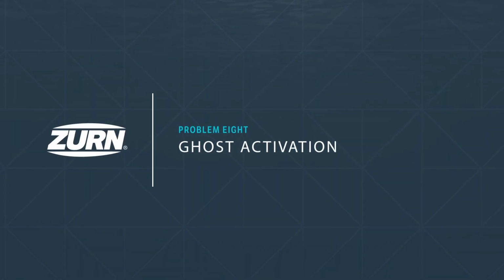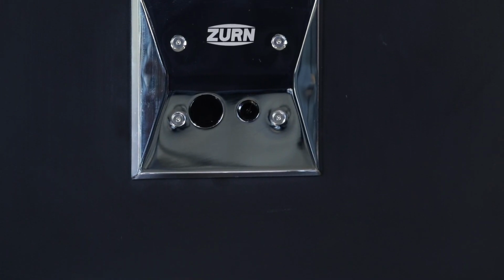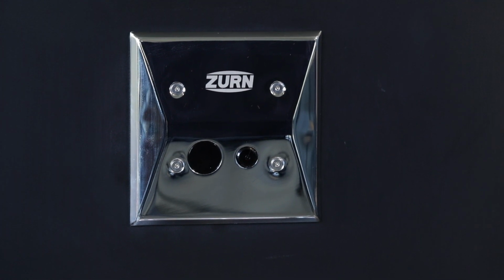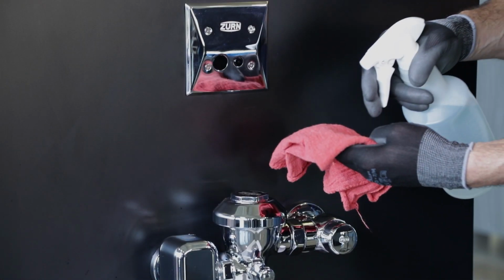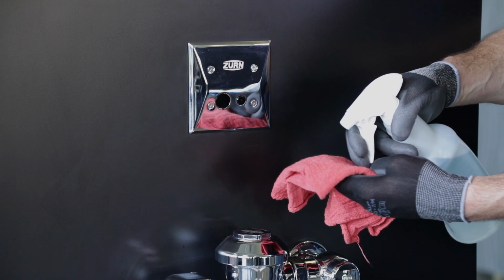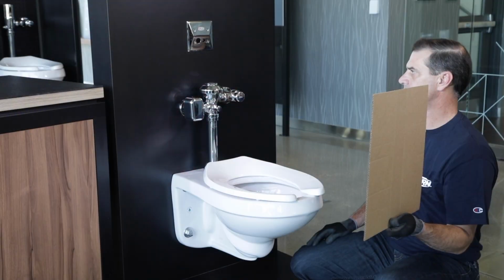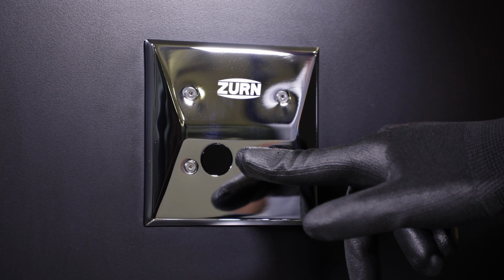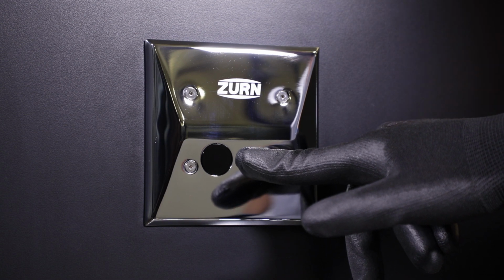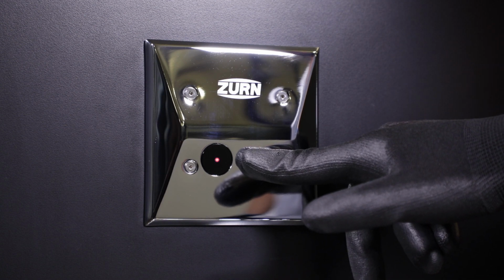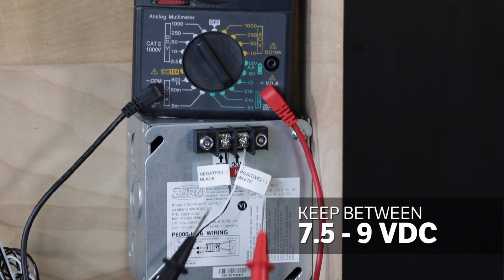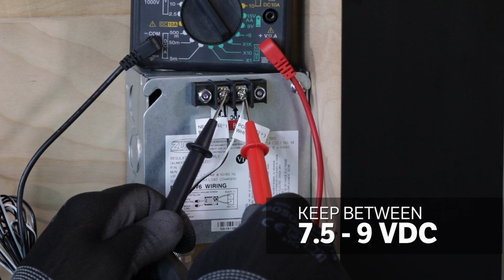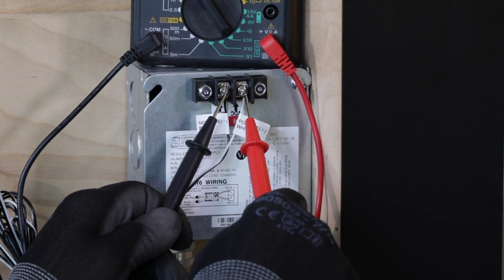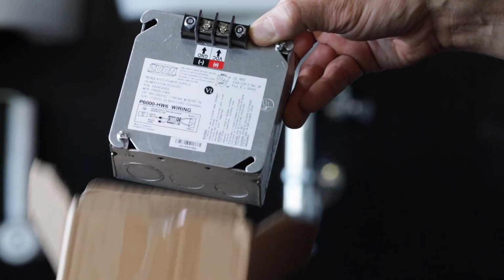Problem 8. Ghost activation. It's not as elusive as it sounds. In fact, we already covered these troubleshooting tips. Here's what you can do. Check the sensor lens first to see if it's dirty. If it is dirty, wipe it clean. The sensor could be picking up an object in the stall area. If the range is too long, try recalibrating the system, as covered during problem 1. Finally, make sure the DC voltage is between 7.5 and 9 volts DC. If there is a malfunction in the power supply, replace it with a new Zurn power converter.